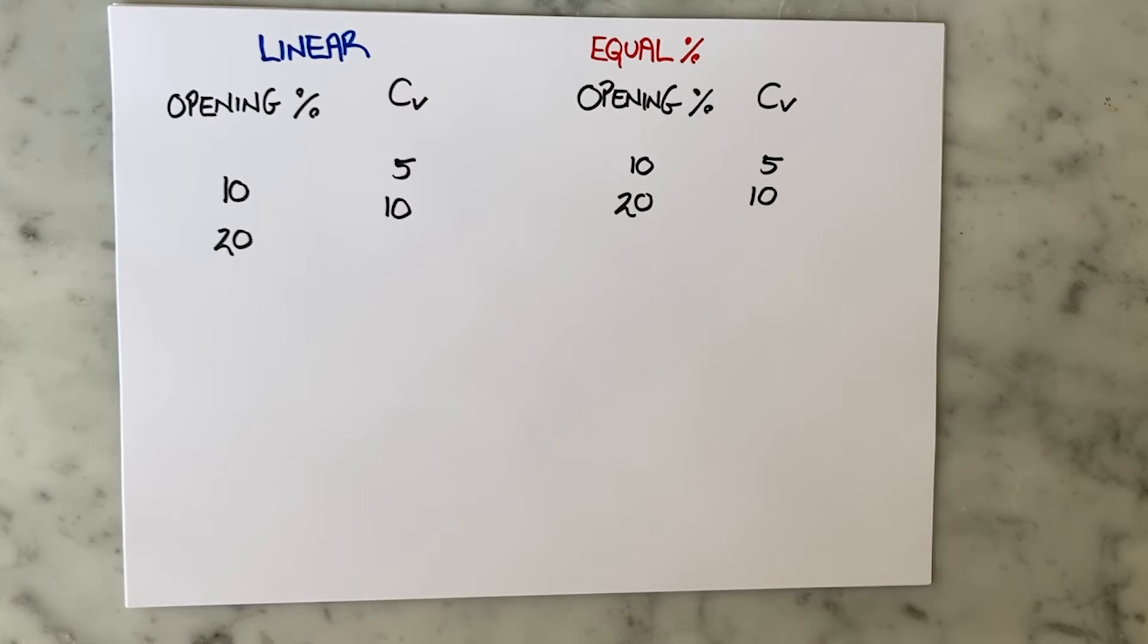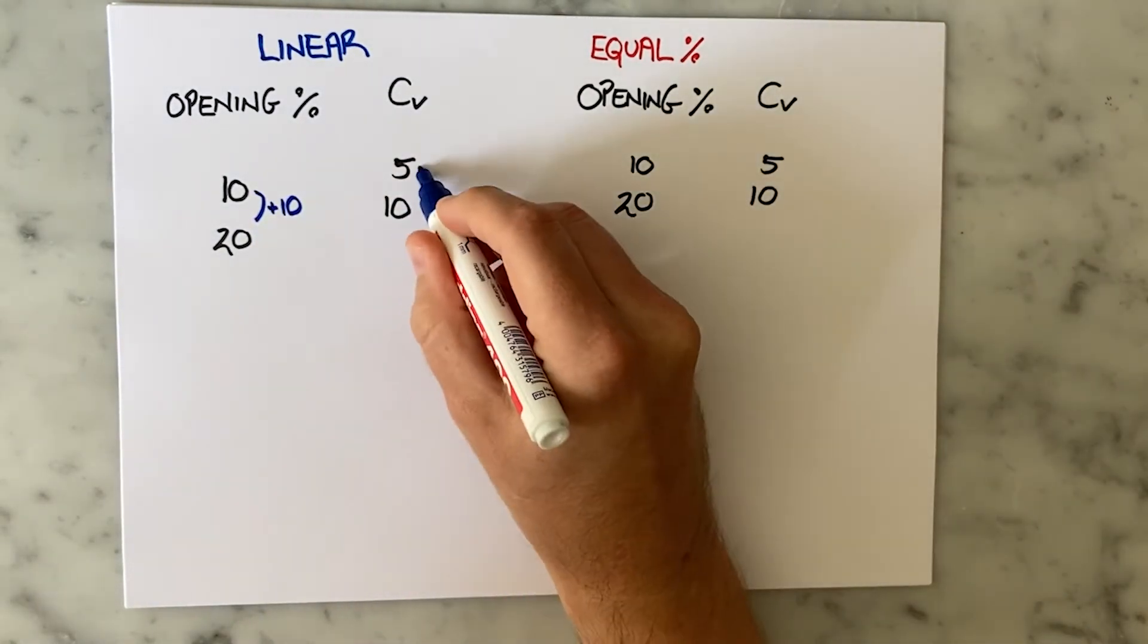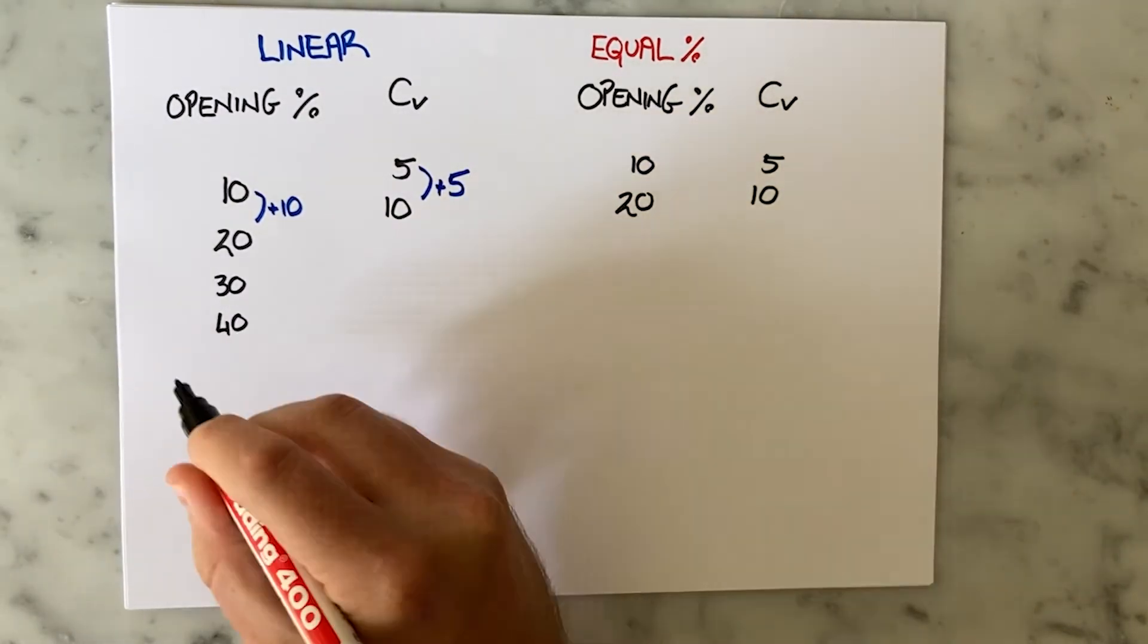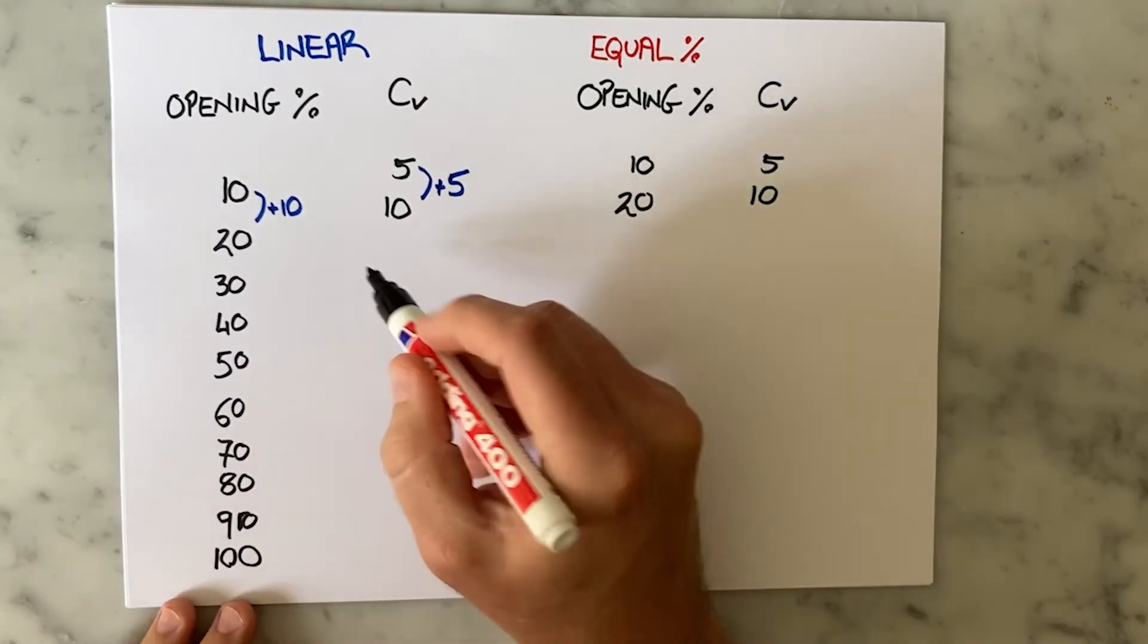The linear valve will carry on adding 5 to its CV for every additional 10% it opens. So at 30% it goes up another 5 to a CV of 15.